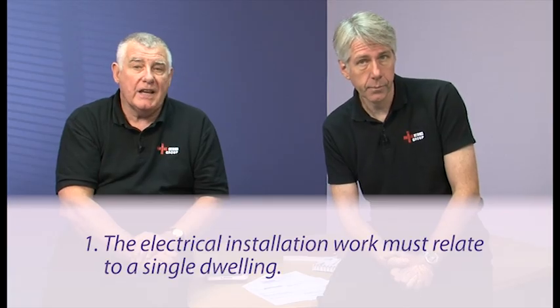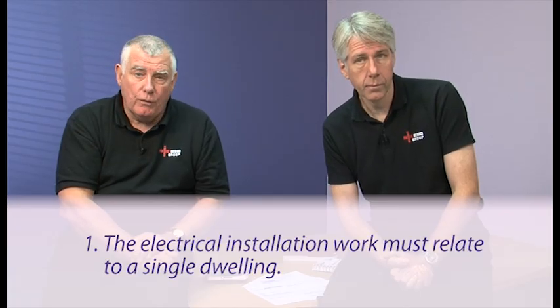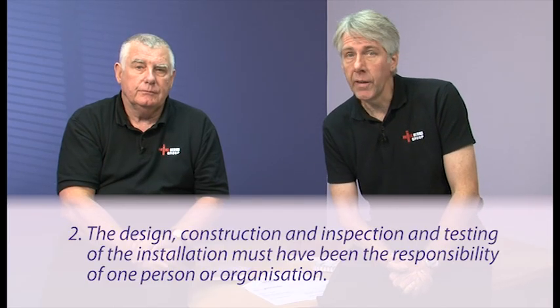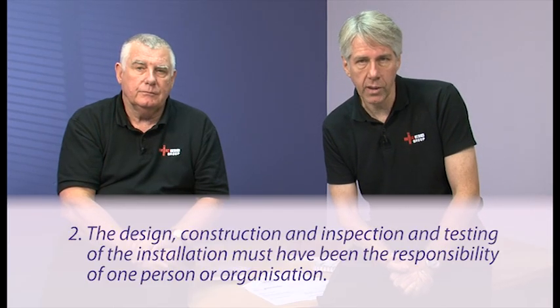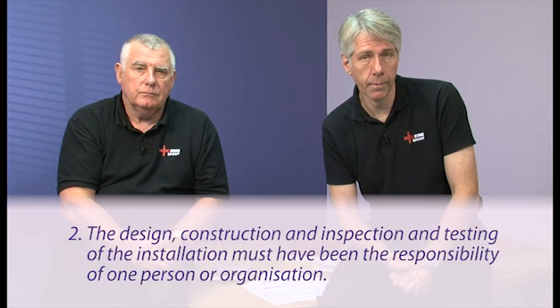If you're going to use a domestic electrical installation certificate, there are 4 conditions which must be met before it can be used. The first is that the electrical installation work relates to a single dwelling. So that's a house or an individual flat. It's not a block of flats or the landlord's supply. Secondly, that the design, the construction and the inspection and testing of the electrical installation work has been the responsibility of one person or organisation.